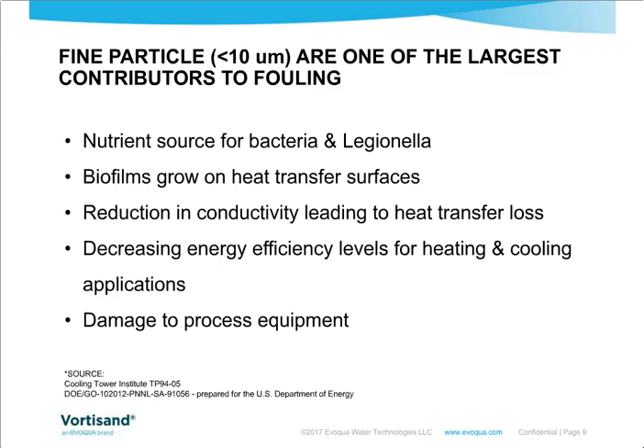Over time, that can cause a significant amount of energy inefficiency. In order to maintain your cooling tower at a certain temperature, you'll need to continually add more and more energy to maintain your certain delta T. So decreasing energy efficiency is definitely a huge part of fouling. And over time, if you have more and more particle growth and biofilms, they can potentially plug up your HVAC units or process equipment, ultimately plugging, damaging and corroding them, leading to equipment malfunction, reinvestment, large capital costs, and operating costs.